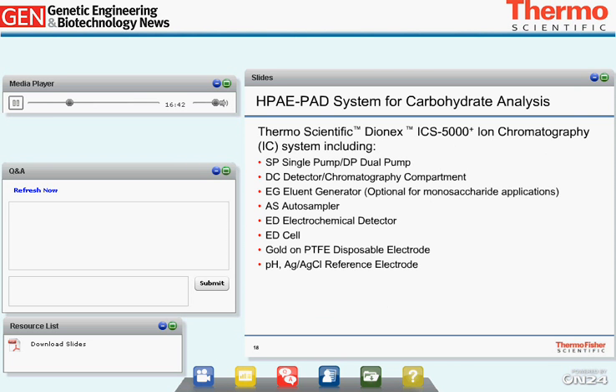The system used for this analysis is an ICS 5000-plus, a polymeric system that can handle sodium hydroxide mobile phases. For monosaccharide analysis, we can use an eluent generator to produce potassium hydroxide mobile phase, which is excellent for automation and eliminating labor. The working electrode is a disposable gold-on-PTFE electrode that can be used for at least a month without polishing, providing greater reproducibility and saving labor.